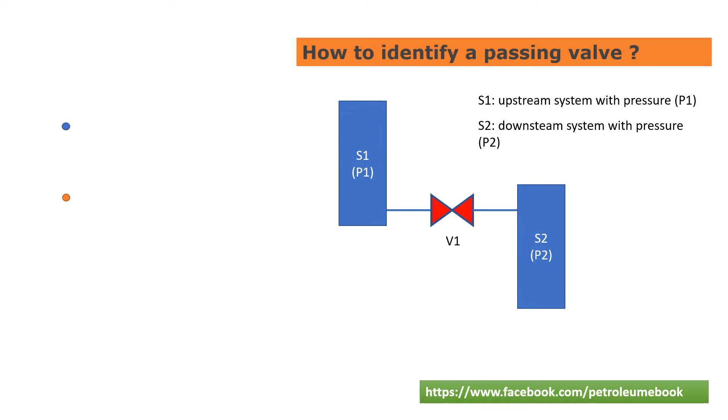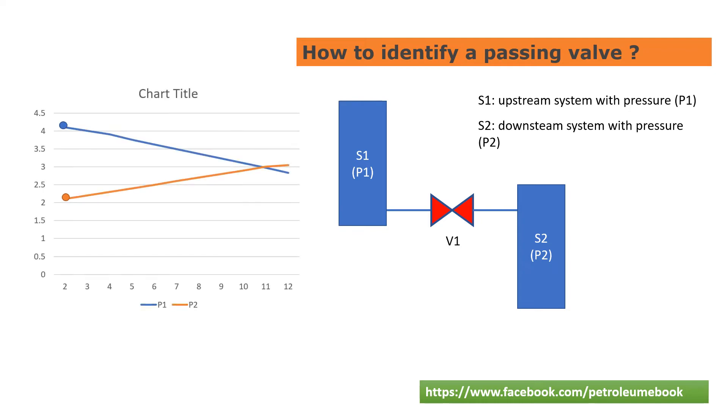The first example is with the systems S1 and S2. After isolating these systems, we see the pressure of S2 increase and S1 decrease day by day. We can conclude that V1 is passing.